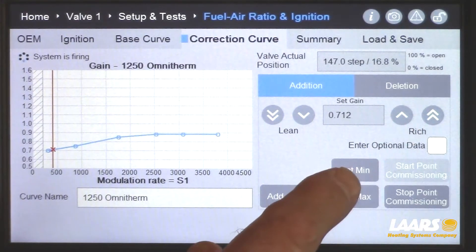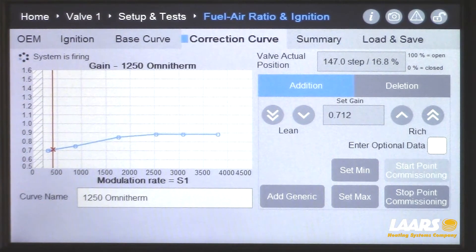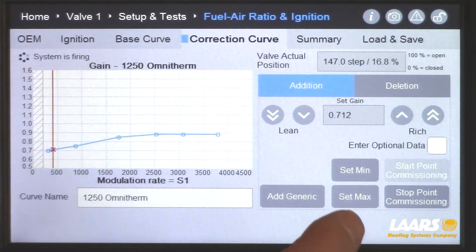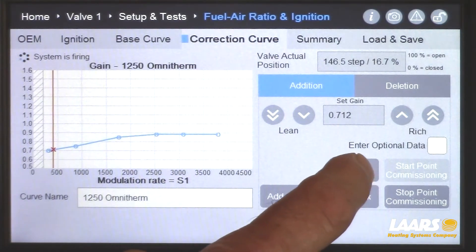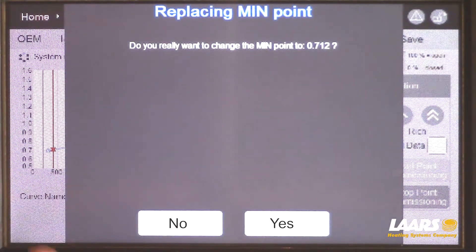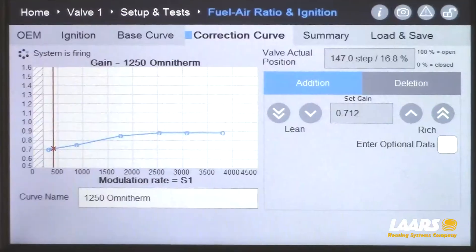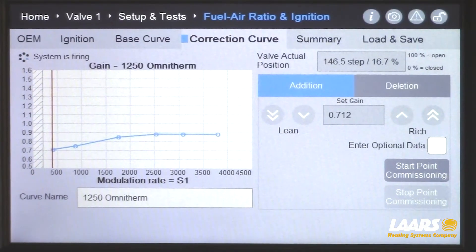This is going to be set min — our low point. Even though we have a point below it, I'll show you how to delete that. This is 1000 RPMs, which is your min fire. We're going to click set min. It's going to ask if you definitely want to save this — click yes. And you'll see it save. So that's set min.